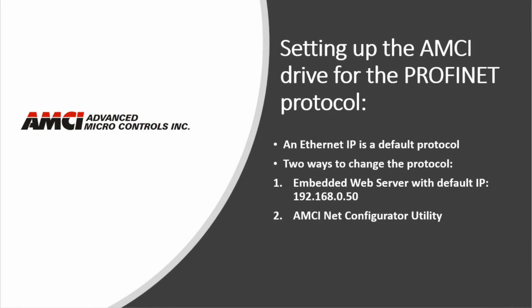All our networked drives with the E2 technology come with three major industrial network protocols available. Those are Ethernet IP, Modbus TCP IP, and PROFINET. As a factory default, the Ethernet IP protocol is active, and that's the reason that we have to set up the drive for the PROFINET protocol.